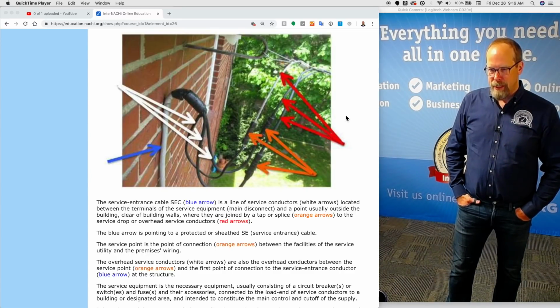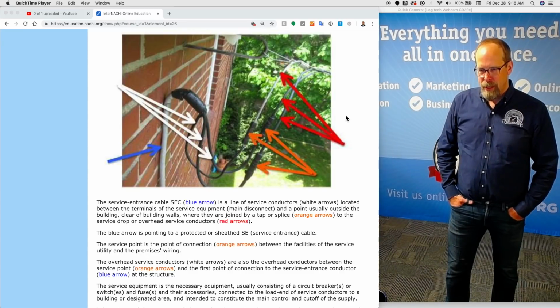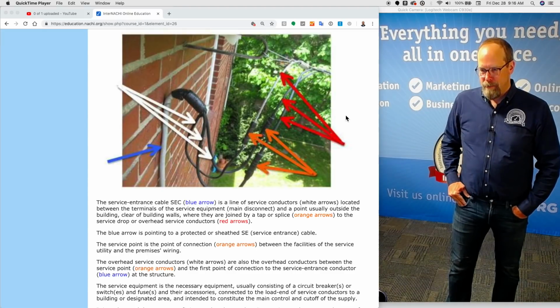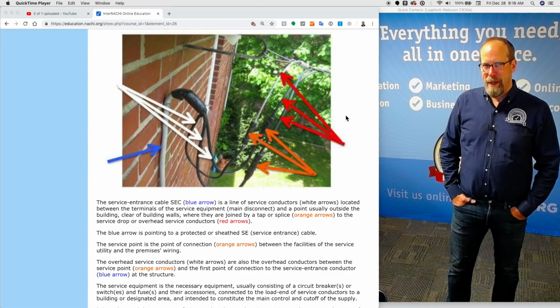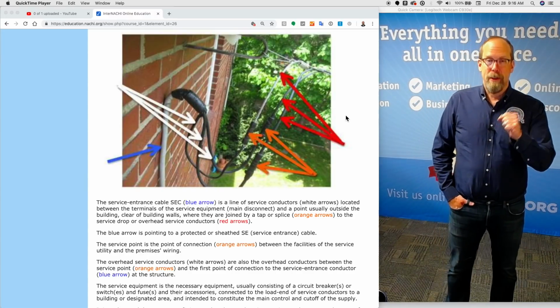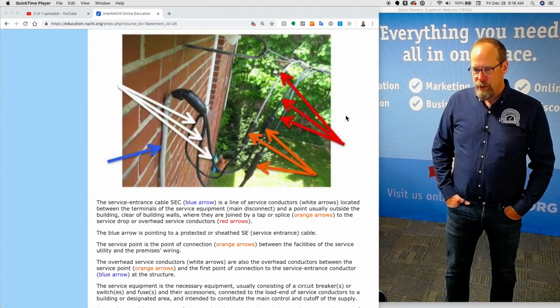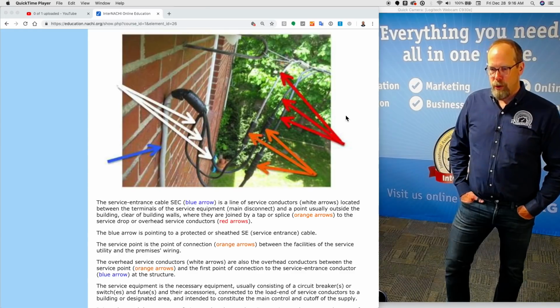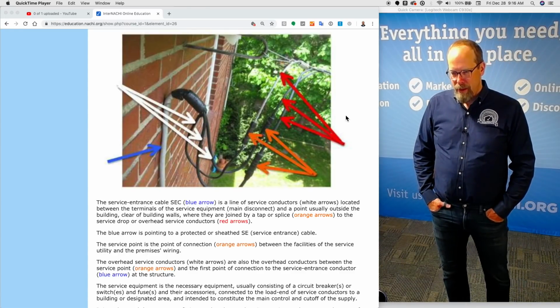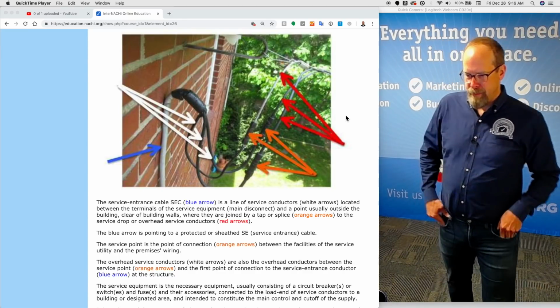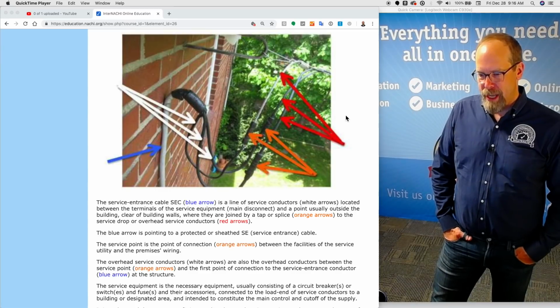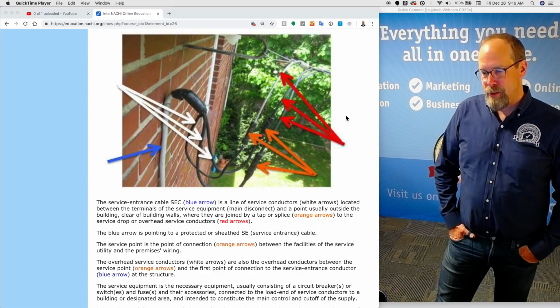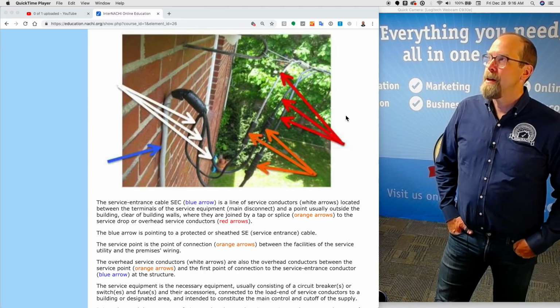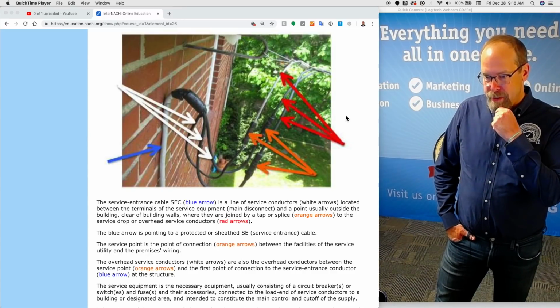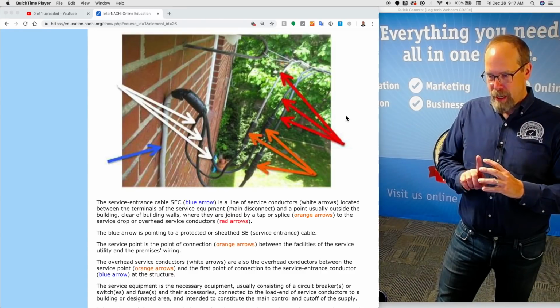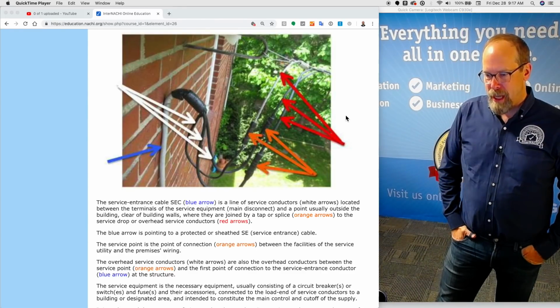And that's the line of service conductors, which are identified by those white arrows. So there's three of them, three big black cables. And they're located between the terminals of the service equipment. That's the main disconnect at the electrical panel, it could be near the meter or the electrical panel. That's the main disconnect. And a point usually outside the building, clear of the walls, where they are joined by a tap or a splice. And that's the orange arrows there. So the orange arrows is that connection. And it's a connection to the service drop or overhead service conductors from the telephone pole, let's say, from the utility company, and that's the red arrows there. So going backwards from the meter that's below the service entrance cable here, SEC, the blue arrow, meter. Imagine it coming up, service entrance cable. That's the line of conductors.